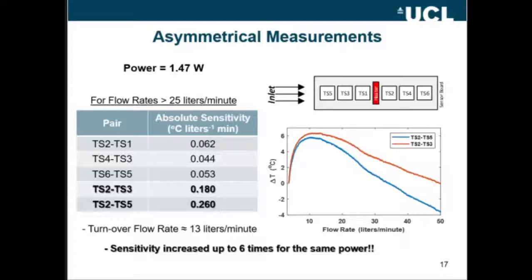You could see straight away that the sensitivity now for flow rates over than 25 liters per minute goes to 0.18, 0.26, that's up to six times larger sensitivity compared to symmetrical measurements.